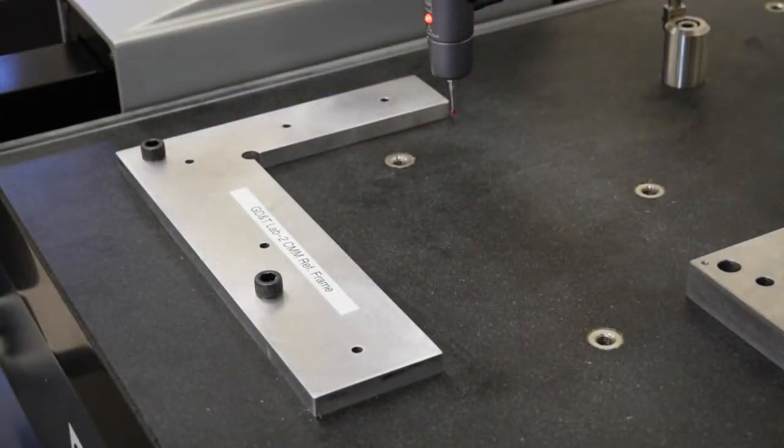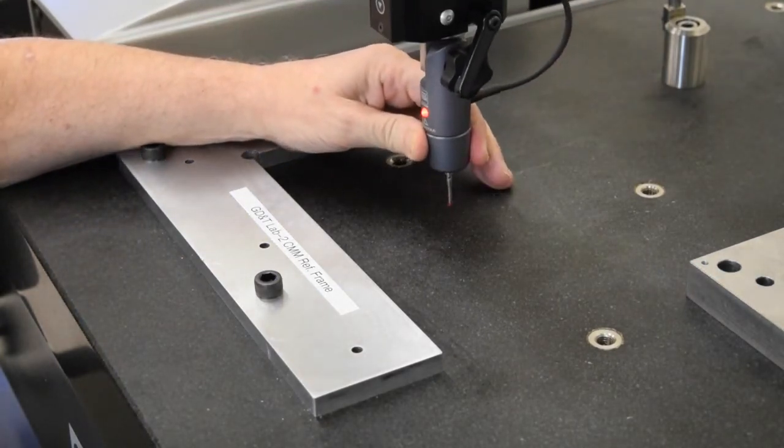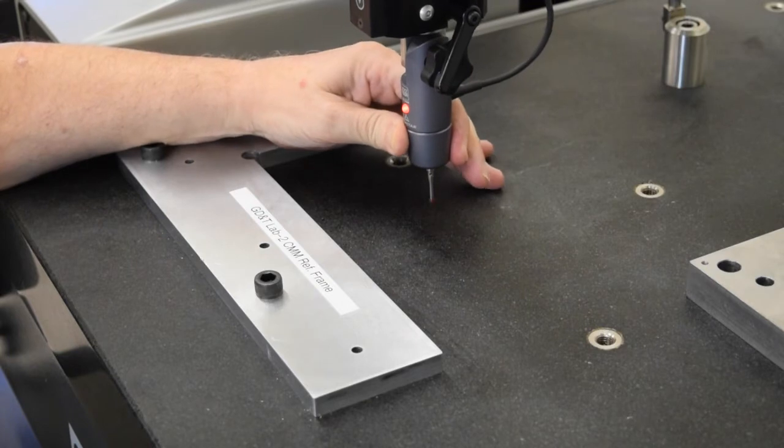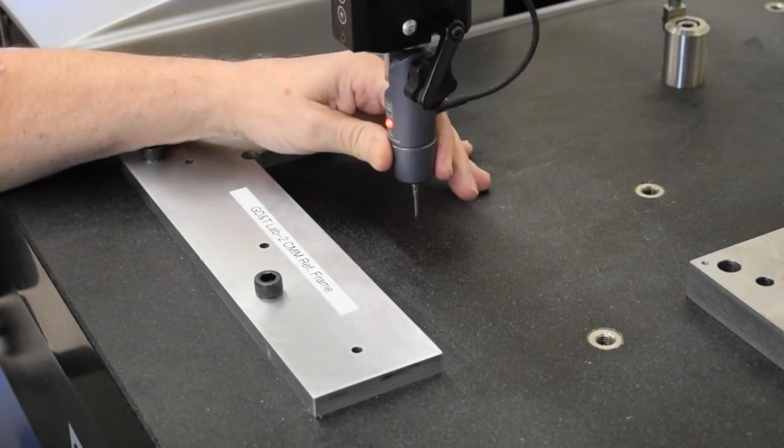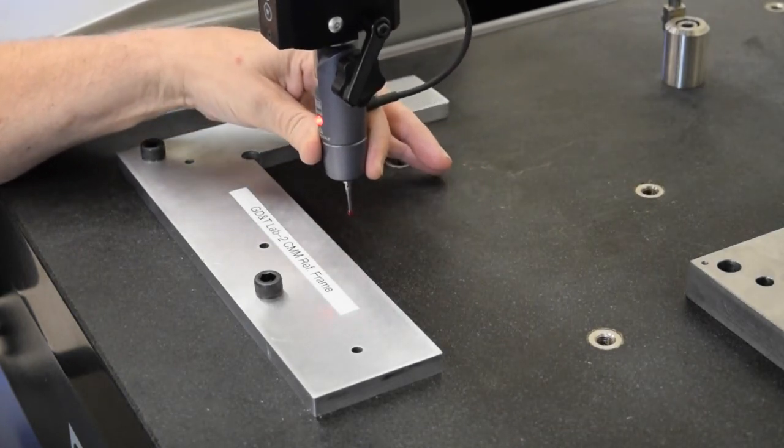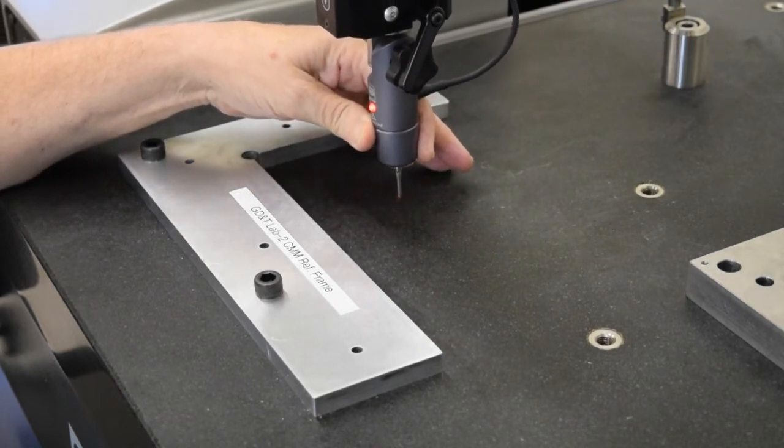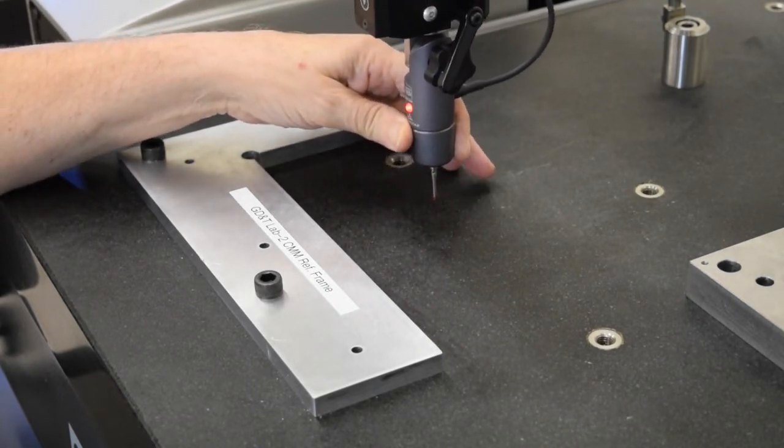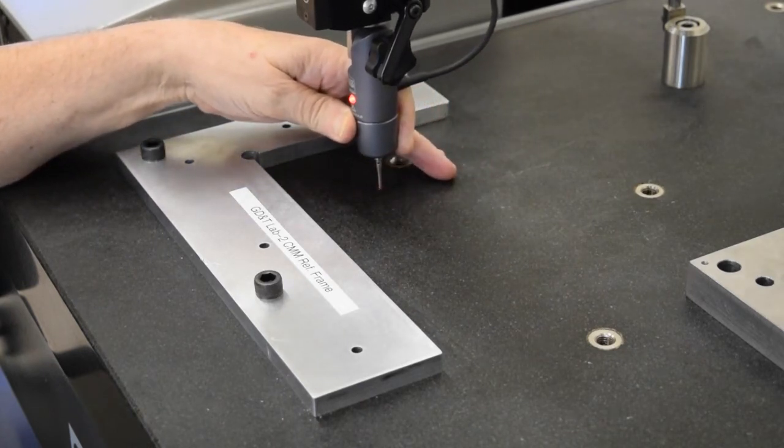Once the probe tip is calibrated, we're ready to start setting our datums. And the first datum, or datum A, is going to be the granite surface plate itself. And we're going to come through and just gently touch the probe to the granite surface plate in a number of places. Use a kind of a zigzag pattern or somewhat random pattern. If you just go around in a circle or a rectangular pattern, it's liable to think you're measuring a circle or a rectangle and not the surface of the plate.